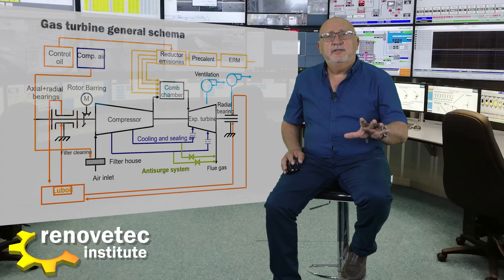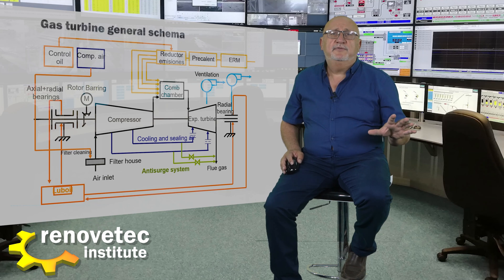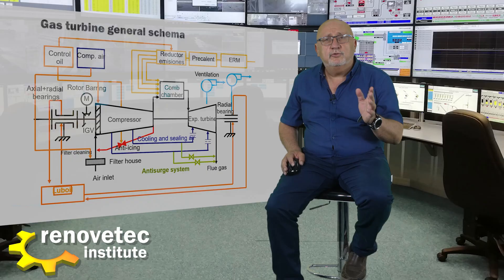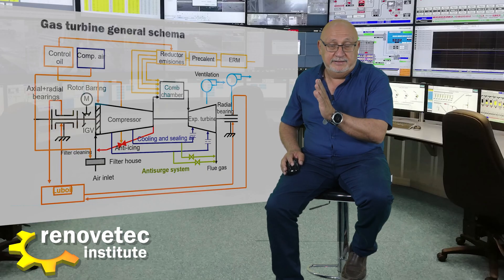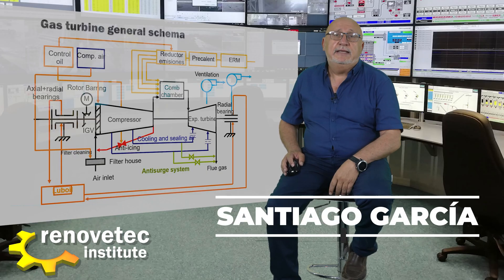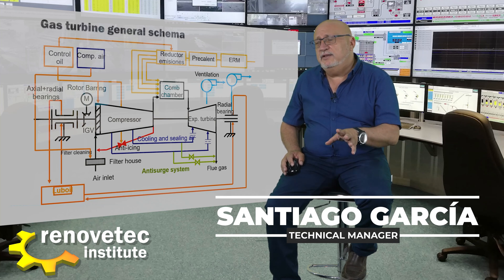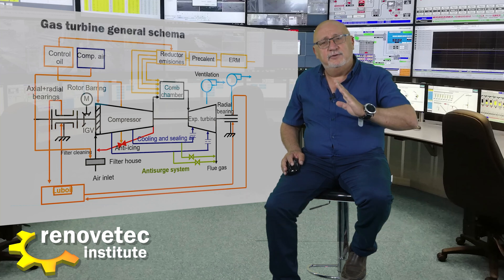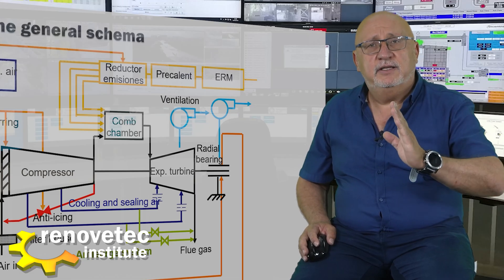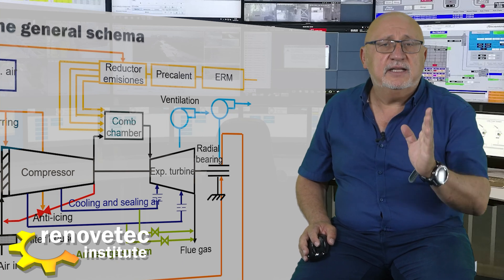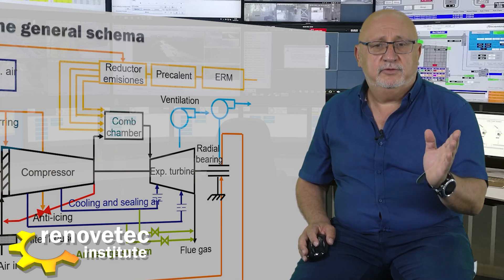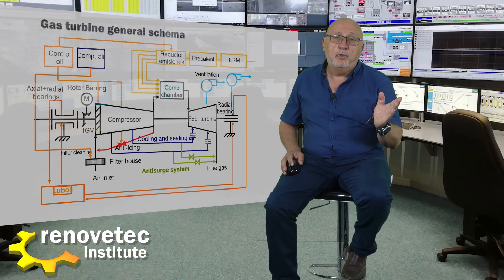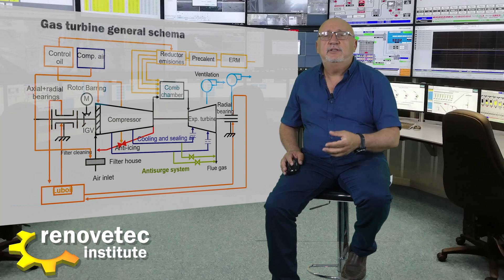The control oil controls the main valve — the valve that introduces the fuel into the turbine — and sometimes also controls the variable inlet guide vanes installed at the inlet of the turbine to control the amount of air entering the turbine.